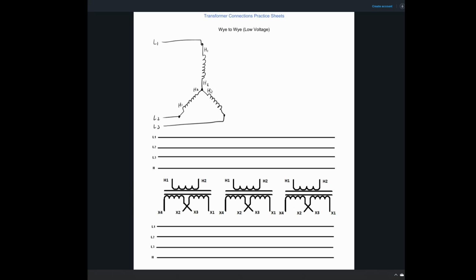So all the 2's are tied together at that common star point, and then we're going to feed each of the H1's from one of these terminals on our line conductors. Okay, if we take a look at here, let's throw in the common core. There was a question on one of the other videos on what I mean by the common core. The common core is the piece of steel that the primary and the secondary are wound around.